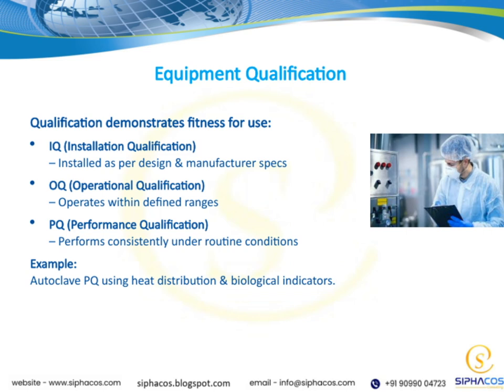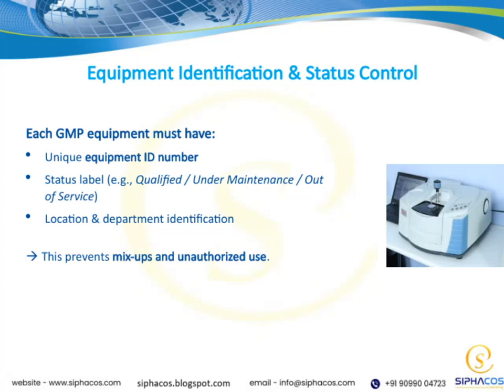our quality processes. Let's talk about equipment identification and status control. Every piece of GMP equipment needs a unique ID number. This helps us easily identify each piece without confusion. In addition, we assign a status label, such as qualified, under maintenance, or out of service. These labels give us instant clarity on the equipment's current condition. It's also important to record the location and department where the equipment is used. All of this together creates a clear, organized system.